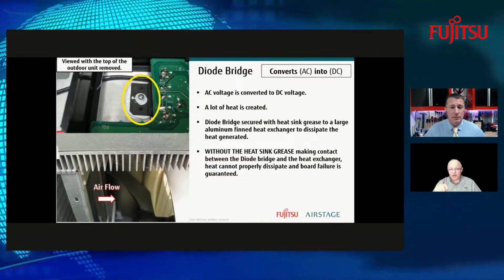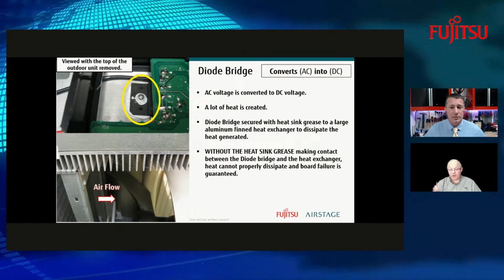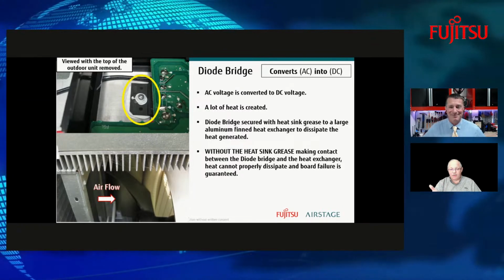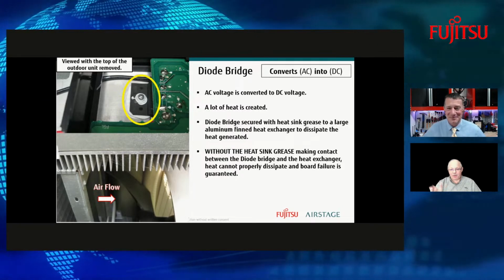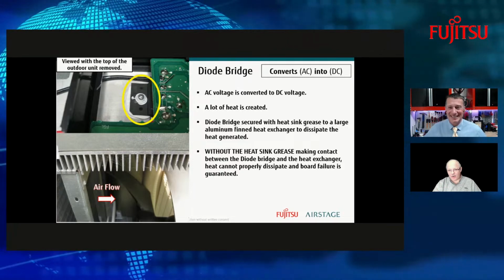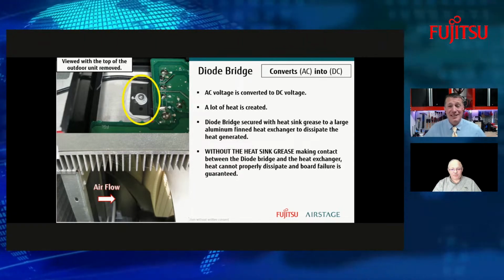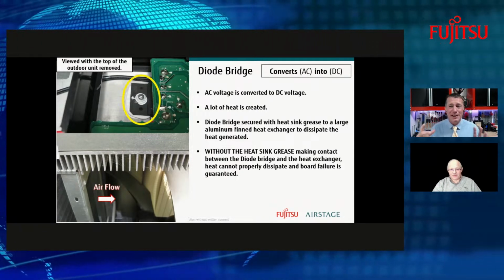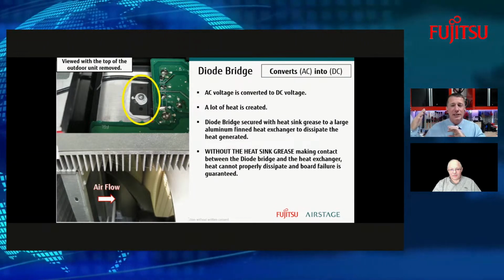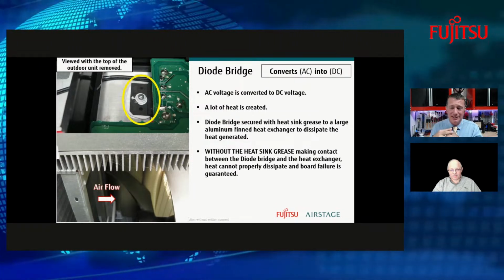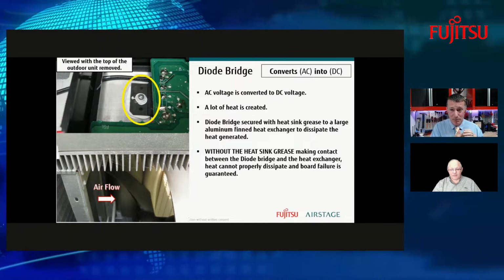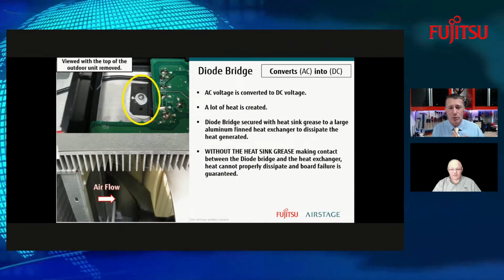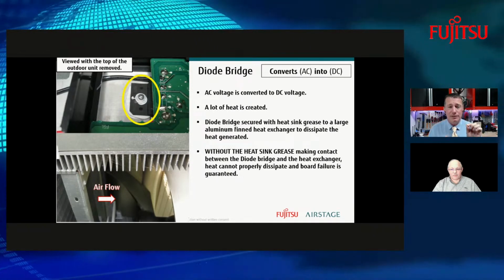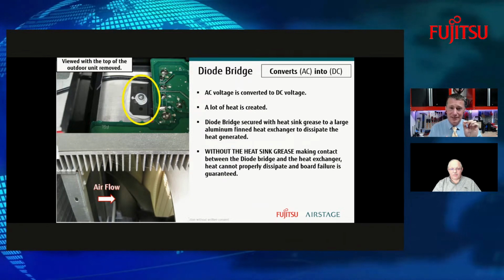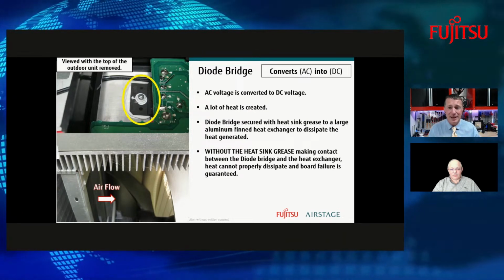If that screw's not down snug and tight, especially if you were to replace that, you'd probably have about 30 seconds and you let the smoke out of the board. Absolutely. I've encountered that many times out in the field, and that's very important to understand: we're converting heat in this process, and that heat must be dissipated away from the control board. And so the heat transfer between our sinks and right on these tabs is absolutely critical.